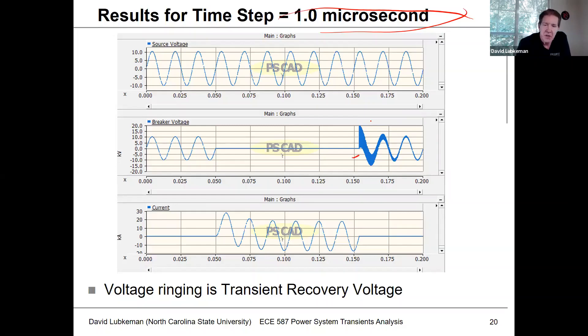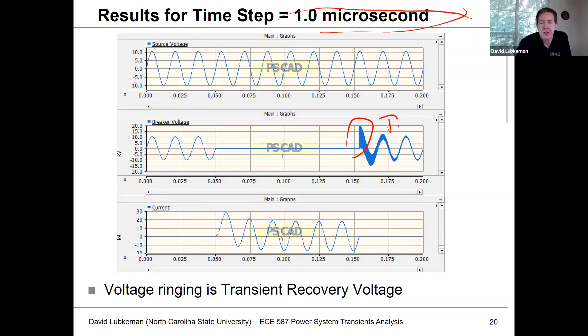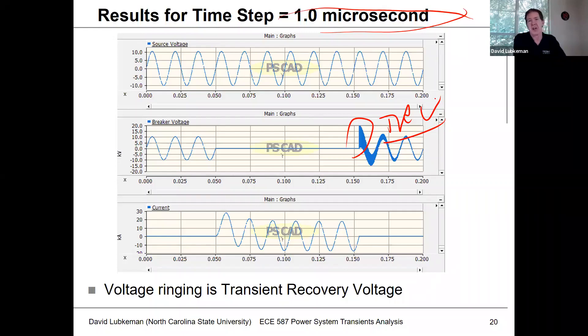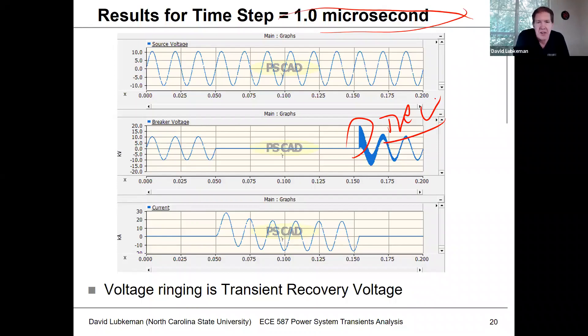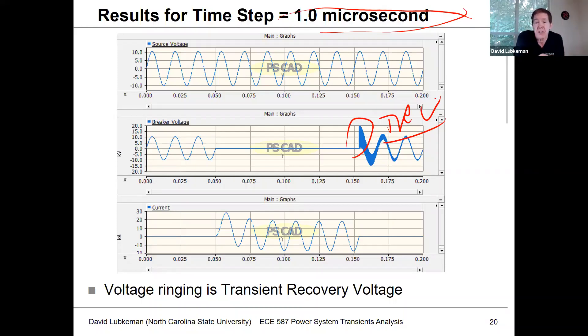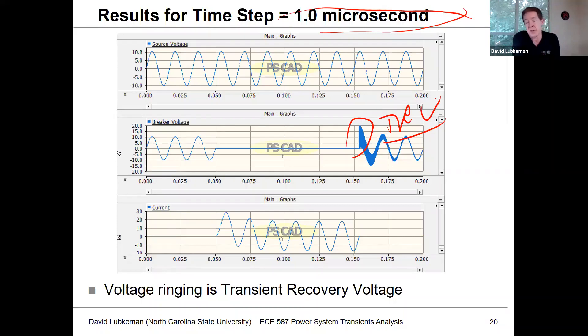But if you drop the time step down to one microsecond, you see a ringing transient on the breaker voltage that can jump up to about two times the nominal voltage. This is what we call transient recovery voltage, which you wouldn't even see unless you dropped to such a small time step because this is such a high frequency phenomenon. Sometimes you don't even see the event with regular recording equipment unless you really drop the time step. This will relate to material covering fault analysis and transient recovery voltage.